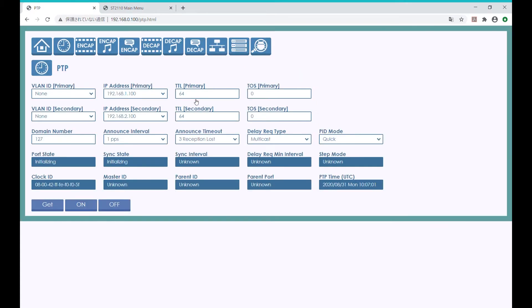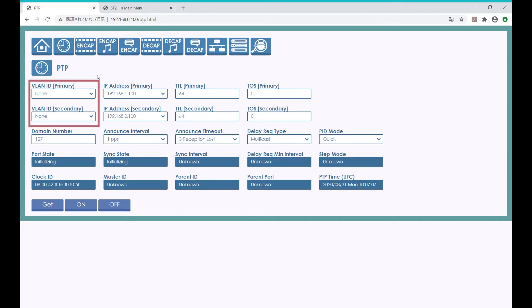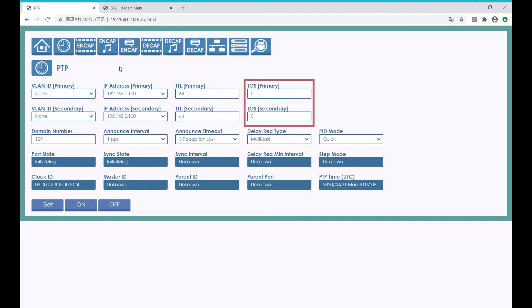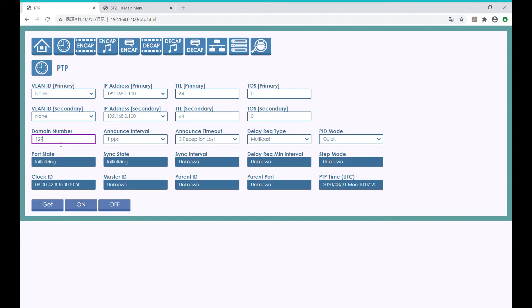As you can see, we can enter primary and secondary PTP settings for VLAN IDs, IP addresses, TTL, and TOS. This one is for the domain number. By entering the domain number of the PTP Grandmaster clock equipment here, the EZ-10 EVK can connect up with the Grandmaster and synchronize the clock.